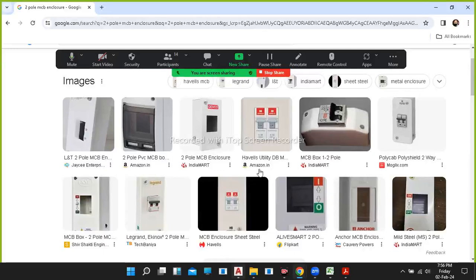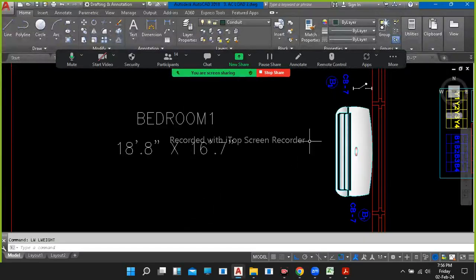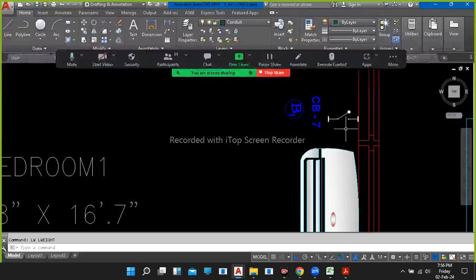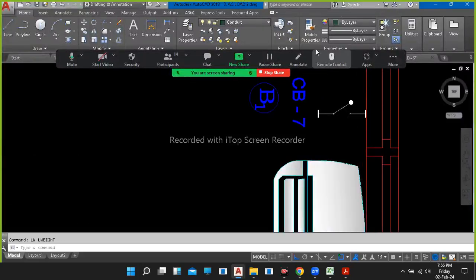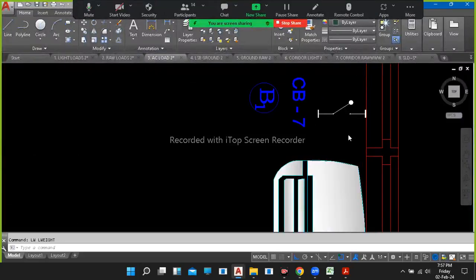Now coming to this, as I told you, you'll get this two-pole MCB enclosure, which you'll put beside the AC. We suggest going only with a two-pole, because if you put a single pole, the neutral gets jointed. So in future, if you want to unplug the AC and there's a neutral joint, or if any current leakage occurs, then in the incomer - which is the RCCB I told you about - if any leakage occurs, the circuit breaker will trip. That's why we best suggest going with a two-pole MCB enclosure.